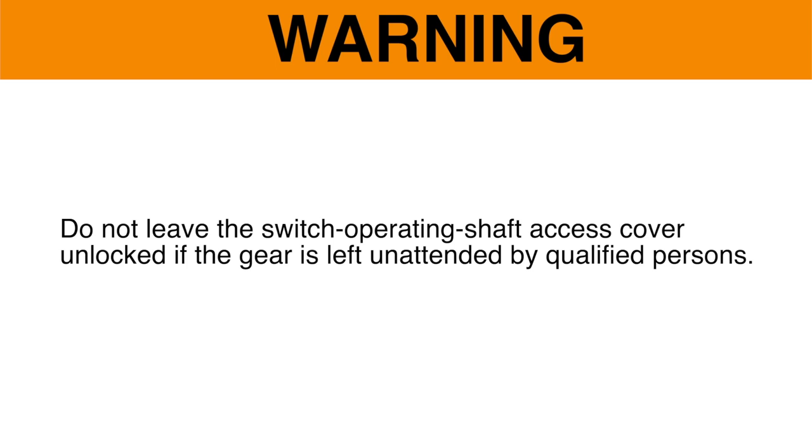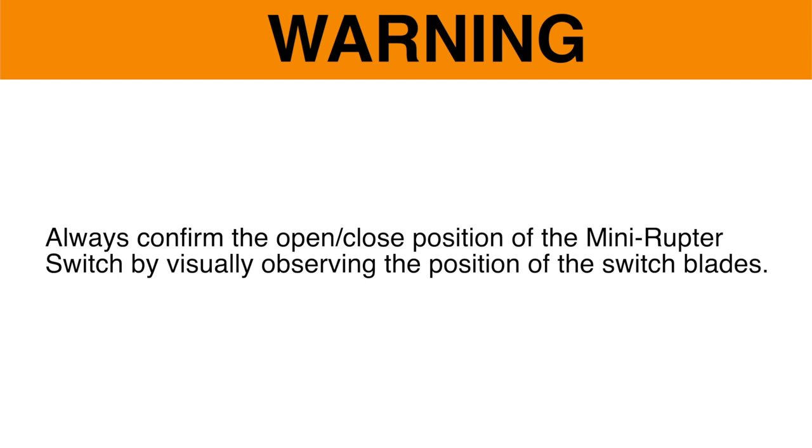Warning. Do not leave the switch operating shaft access cover unlocked if the gear is left unattended by qualified persons. Always confirm the open-close position of the Mini-Rupter switch by visually observing the position of the switch blades.